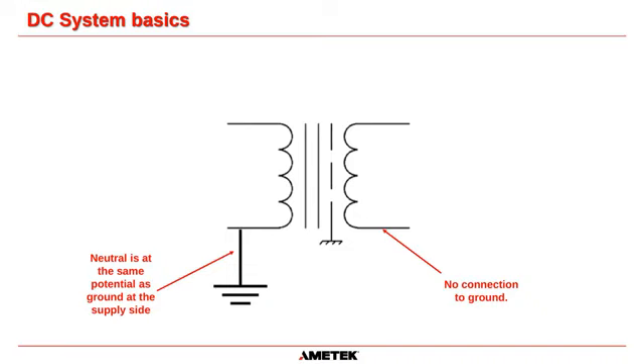So therefore, when we introduce a transformer that has isolation, galvanic isolation, in other words, this winding here has no physical connection to this winding here, none whatsoever. There is an insulated gap between those two points. They are not electrically connected. As we've just mentioned in that previous slide, the neutral is usually always connected to ground from the main transformer, whether it's in a house or in an MCC in a plant. But if you put a transformer that has isolation in there, then the secondary of that transformer has no connection to ground whatsoever. None.